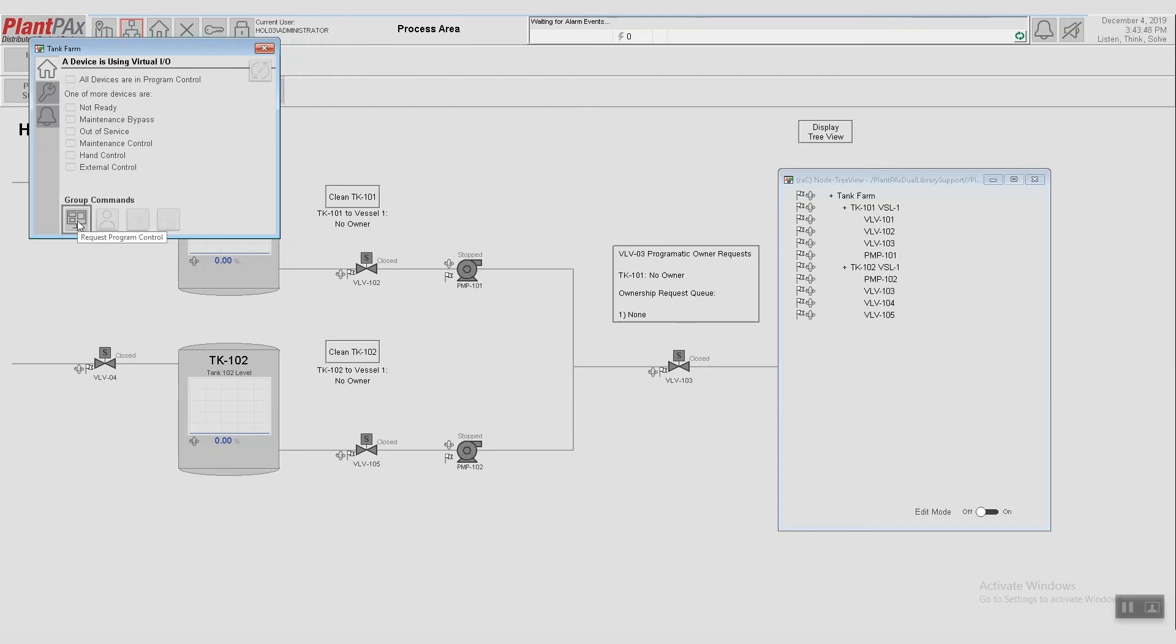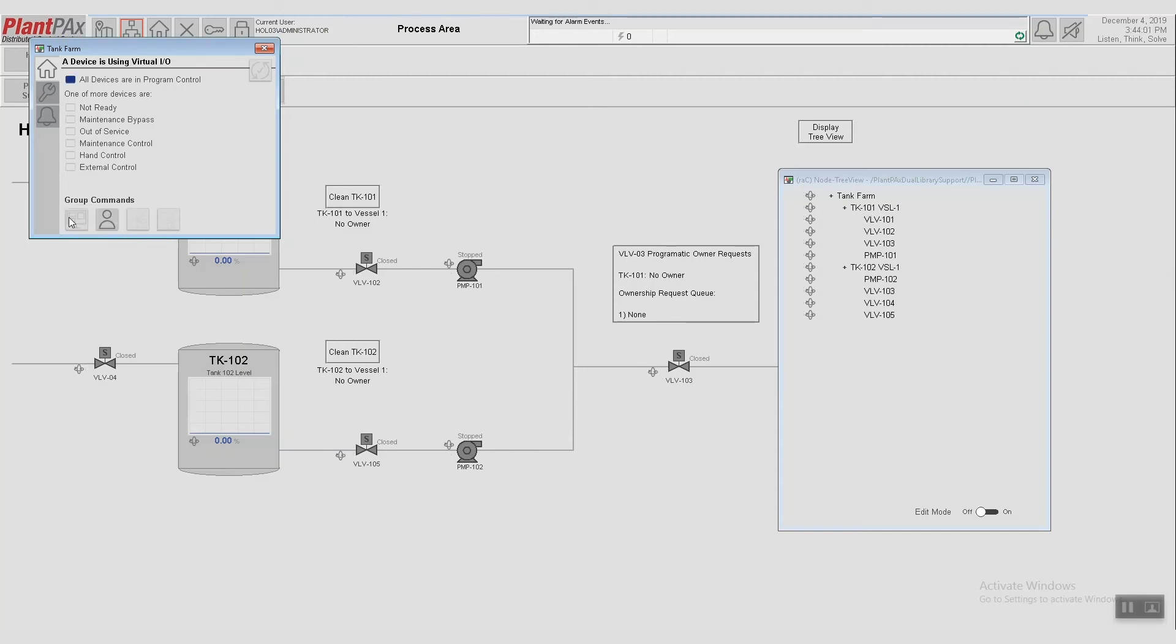And so what we can do is request program control. So right now, everything is in operator mode, which you can see from this white flag. If we request program control from the highest level, we issued one command, and that propagates down through all of the devices. So instead of having to open the faceplates for all seven devices and do this one by one, we only need to issue one single command.